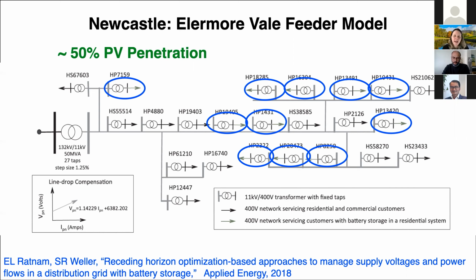Here our edge of interest is the 132 to 11 kV transformer, because that transformer is quite expensive to upgrade, and it is overloaded during one of the hottest days of the year, which we'll look at in a moment. So air conditioner load was driving the peak.